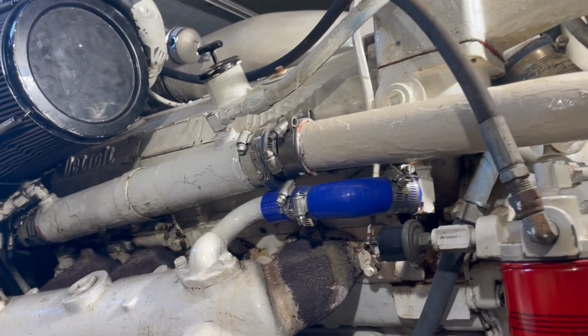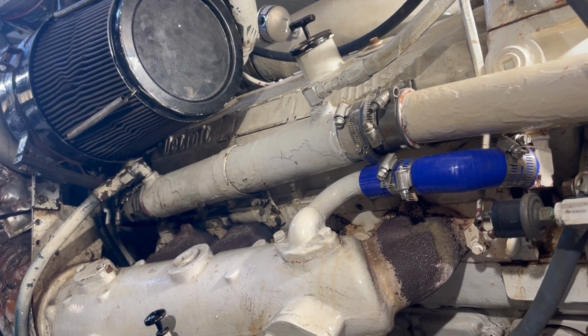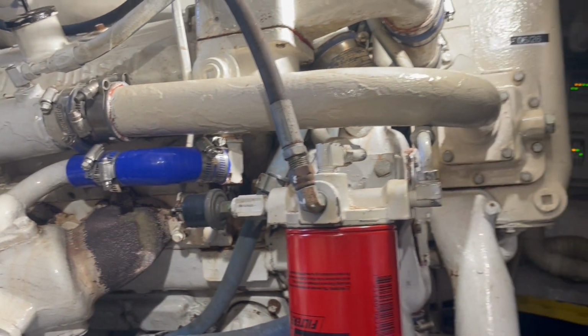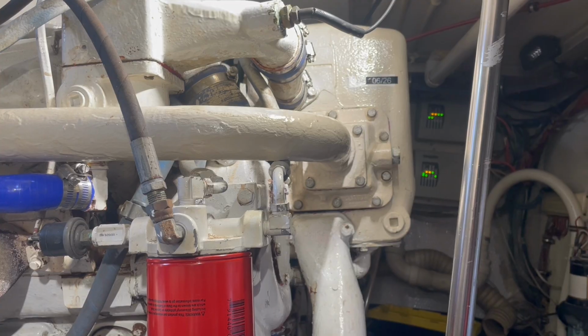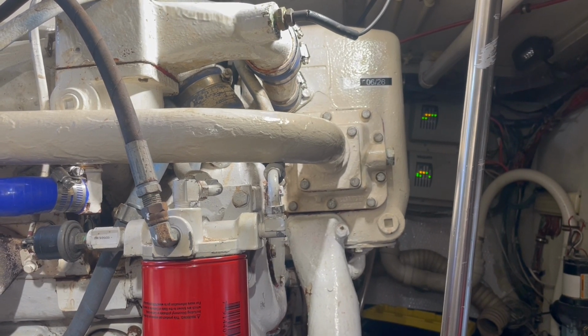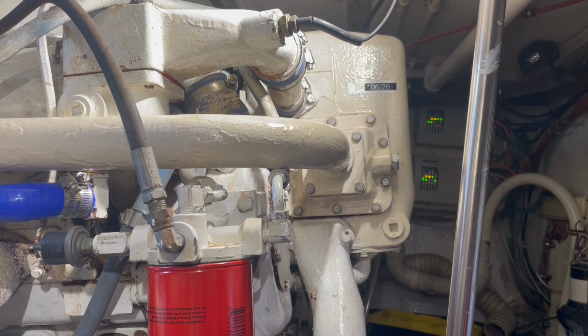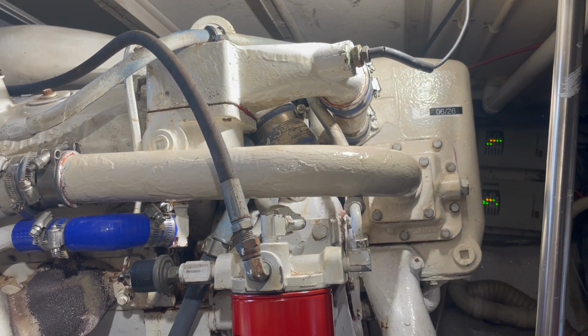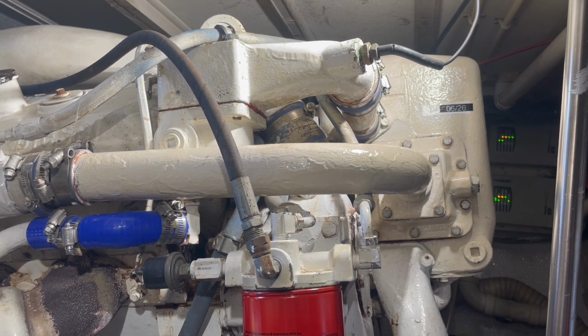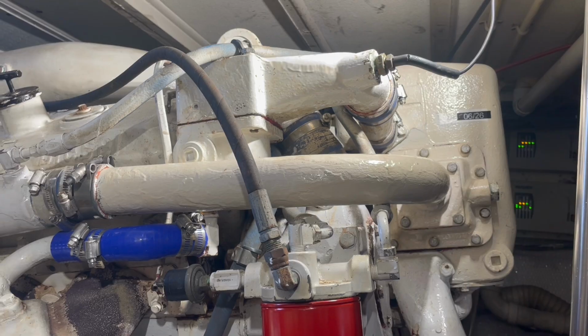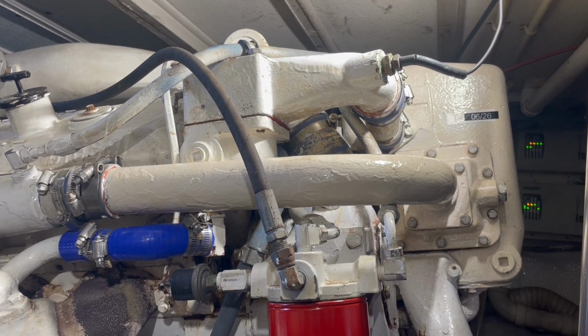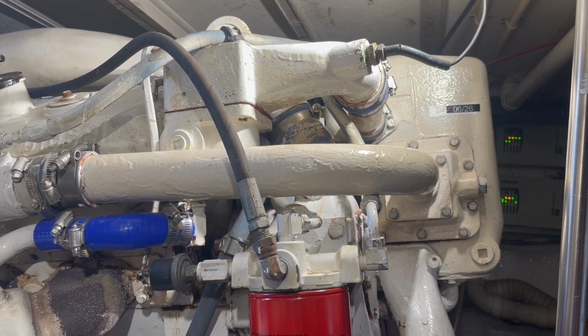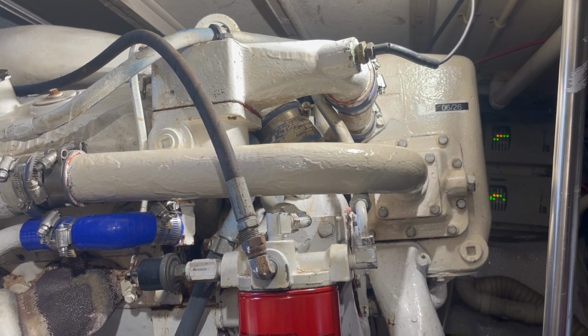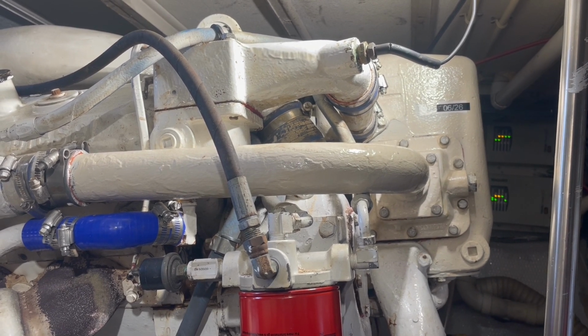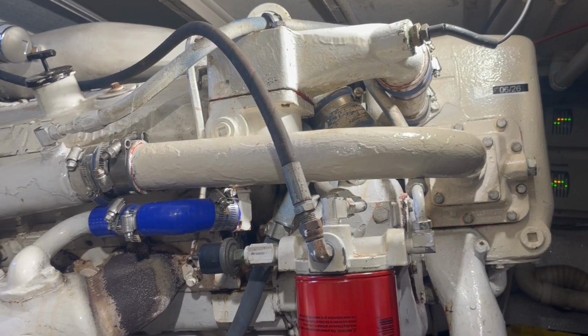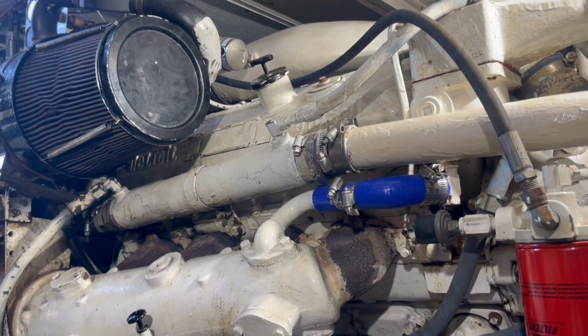Today I want to go over the procedure for cleaning the heat exchanger and the cooling system in place without removing it. First, I'd like to say that cleaning a heat exchanger in place is not the recommended procedure. You should pull these heat exchangers out from time to time and have them pressure tested and cleaned in a radiator shop by a professional.